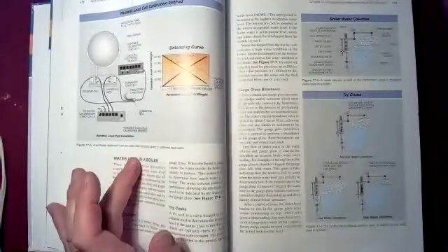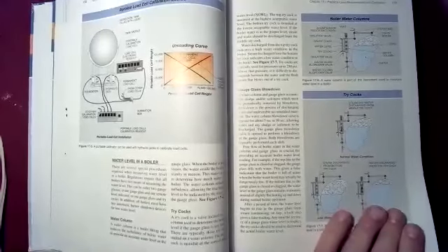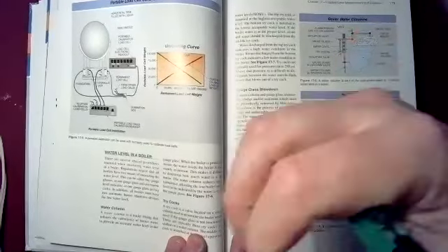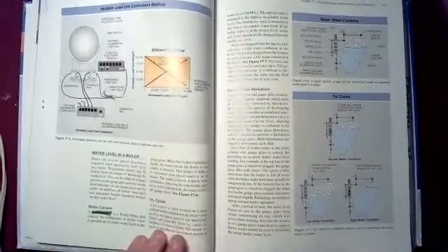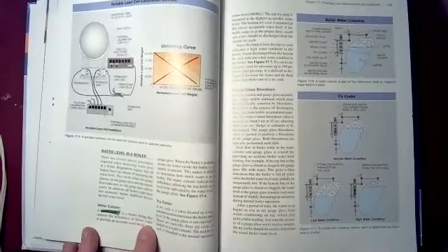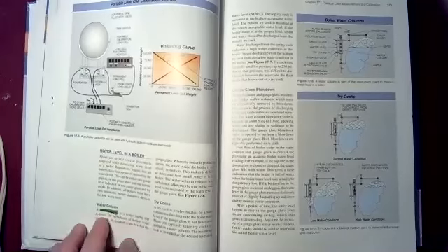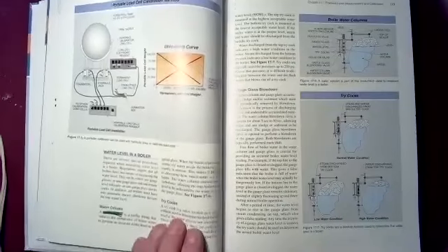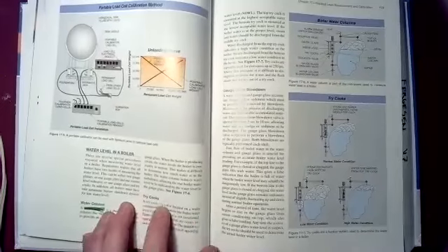It talks about some common problems with water levels in a boiler and the challenges with measuring that. Mentions a few key terms in here. Water column, key term for boiler water levels. Fitting that reduces the turbulence of boiling water, provide an accurate water level. So it basically takes the hot water away from the rest of the boiling chamber and puts it into a column of water where you can measure the level accurately. Try cocks are basically spigots that you can open up to test to see if there's liquid at that level.